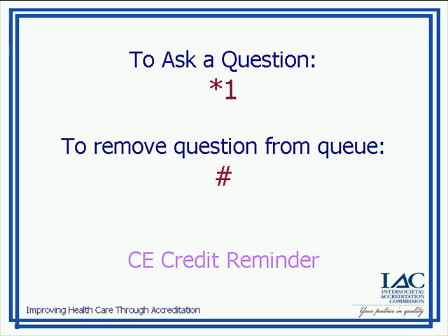We have a lab where we have a workstation and the imaging table. It's not very much, probably about 8 feet or 10 feet apart. Is that adequate? The answer is it depends. What you're going to need to do is you may need your physicist to help you do this. You're going to need to see if you're getting doses out of your hot lab and walking in front of the camera, if you're getting shine through onto your camera.